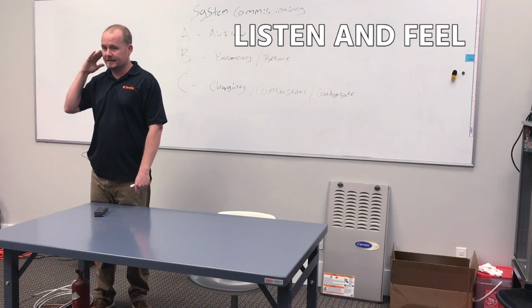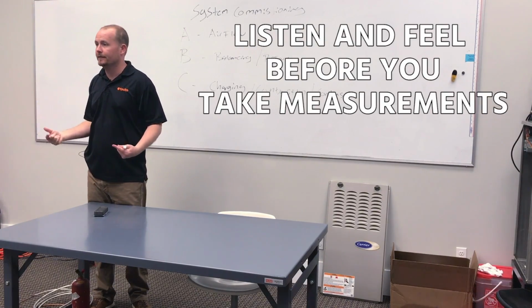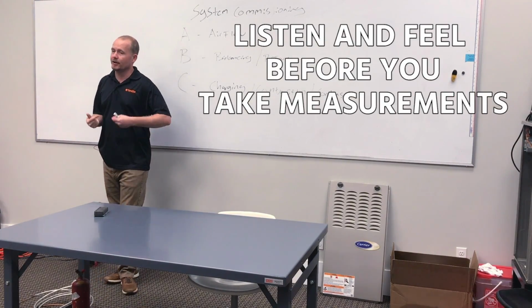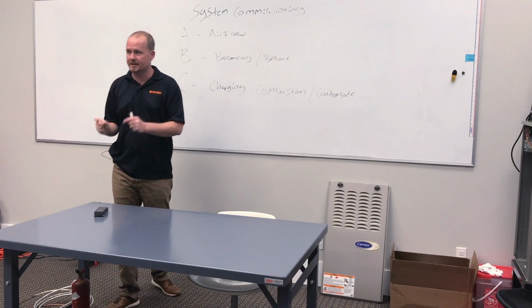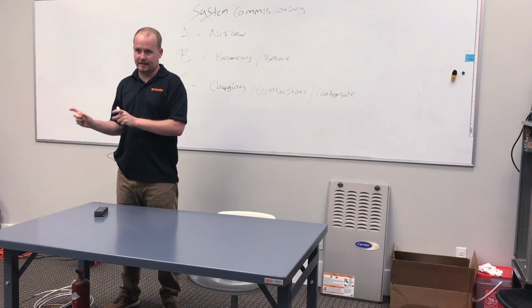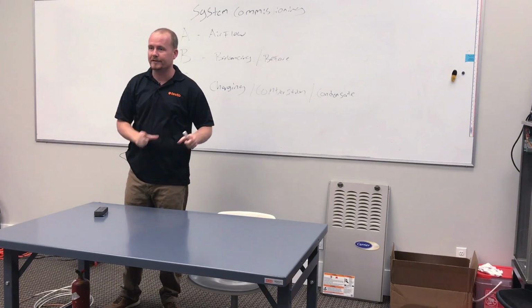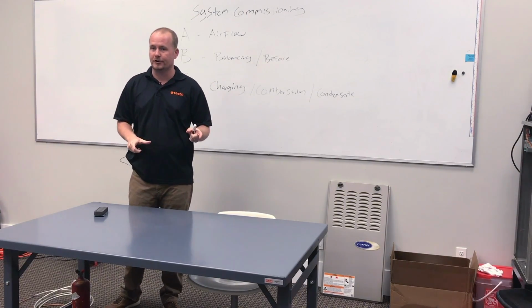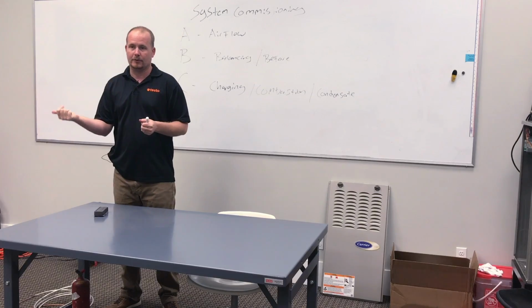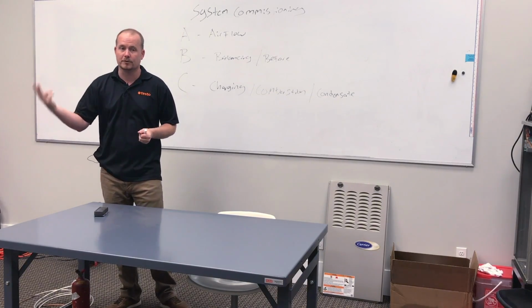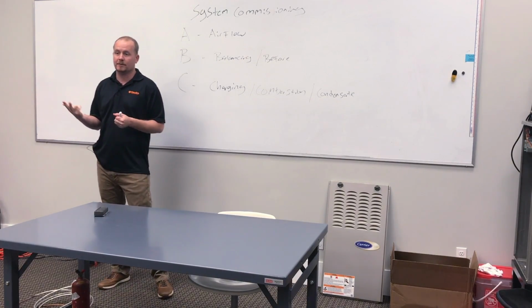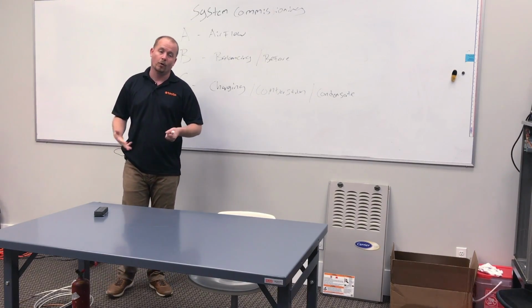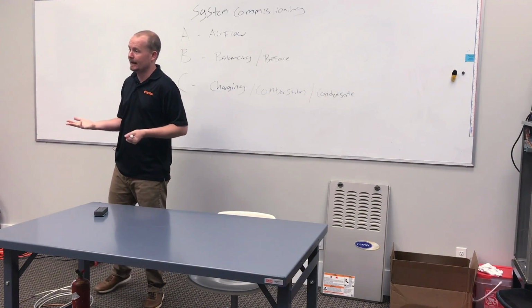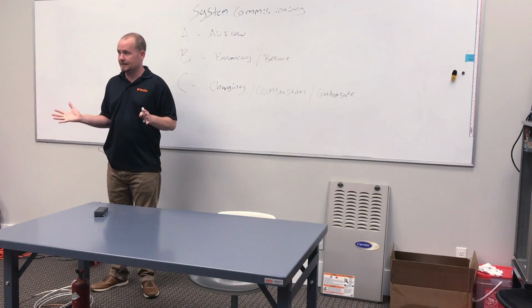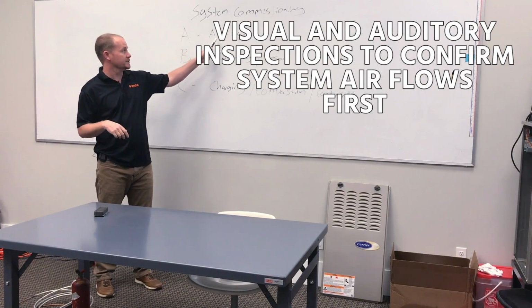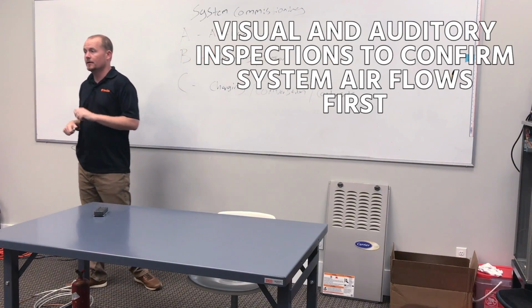Good technicians listen and feel before they start taking measurements. There's nothing worse than a technician who knows the measurements to take, but misses the obvious things that lead up to before you even take that measurement. Like, why would you check your refrigerant charge if your condenser fan motor was running backwards, or your blower motor wasn't running, or your blower motor was running so slow that it hardly mattered because it wasn't getting the proper calls, like we've talked about, or your filter's so dirty that it's barely getting any air through it? Those are all pointless tests. So you always do your visual and auditory inspections to confirm your system airflows before you do anything else.